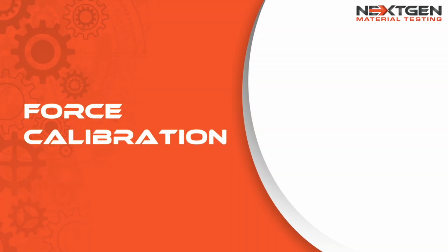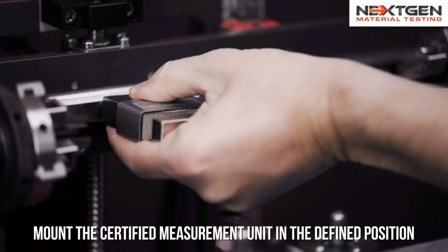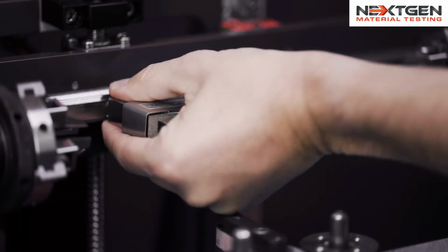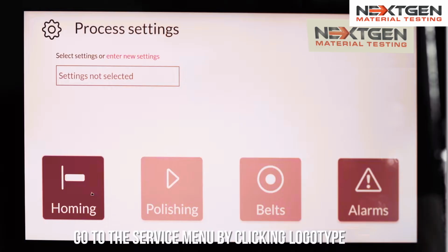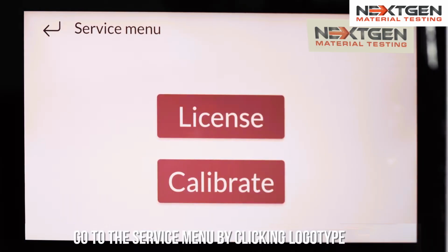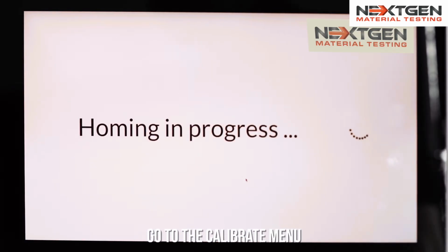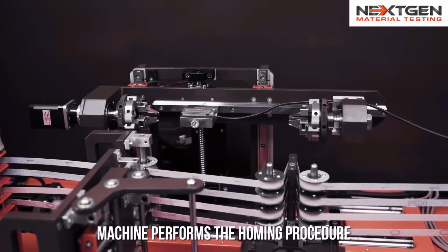Force calibration. Install certified measurement unit in calibration position. Access service menu via logo. Open calibration menu. Machine runs homing procedure.